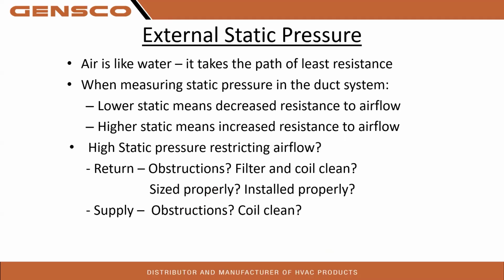Obstructions could happen later down the road. Did a critter get in there and chew through the ductwork? Or up in the attic space, they just had a new roof put on and the roofers were crawling through the attic space and crushed all the ductwork? Or the homeowner was running some new speaker wires for a surround system. Those are all things I've run into, where I've gotten up there, cleared out the insulation, and then realized that I had some crushed ductwork that needed to be repaired. And the only way I could tell that without actually going up there digging around was to check my static pressures.